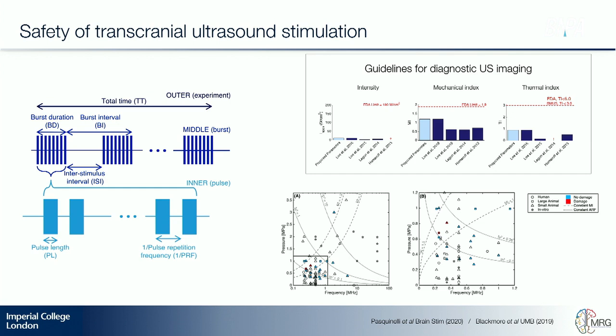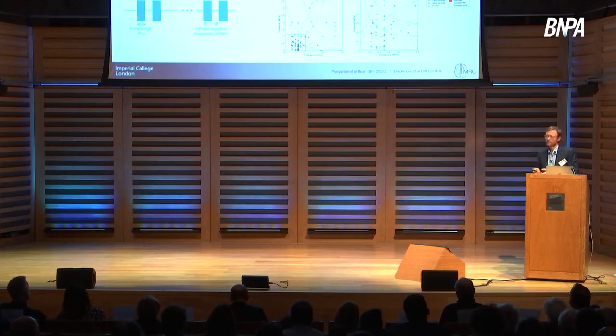But basically, the important thing to say is that the existing guidelines for ultrasound safety are out there for diagnostic imaging, okay? And the FDA levels are up here, and you take into account the amount of pressure that is generated by the ultrasound. There's a thing called the mechanical index, and the amount of temperature rise which you get as well. And all the studies so far, including our own in light blue here, are well below those levels. However, the way in which ultrasound is delivered is very different from imaging. So as I said, in imaging, it's a single pulse, you wait for it to come back, and then you scan somewhere else, and it's a single pulse, and you wait for it to come back.